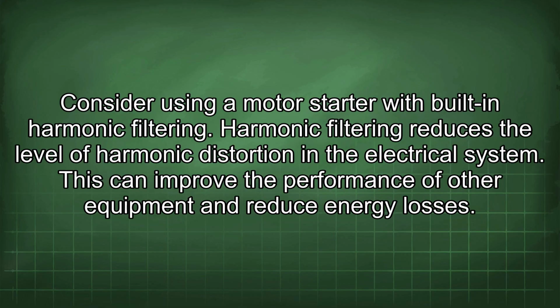Consider using a motor starter with built-in harmonic filtering. Harmonic filtering reduces the level of harmonic distortion in the electrical system. This can improve the performance of other equipment and reduce energy losses.